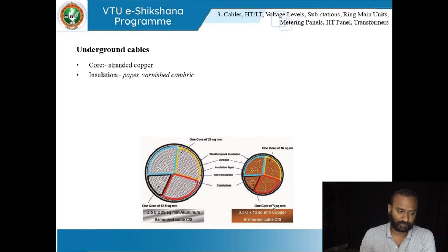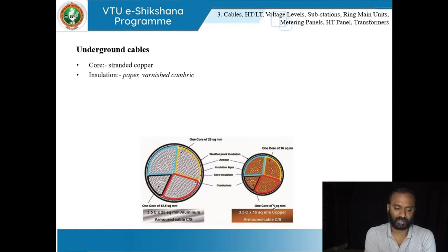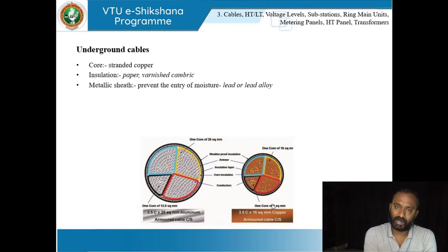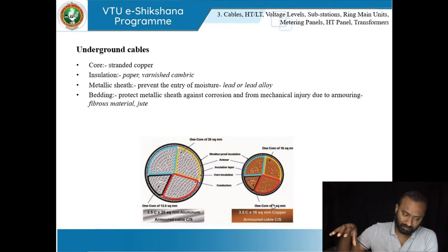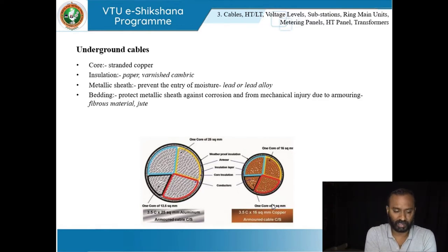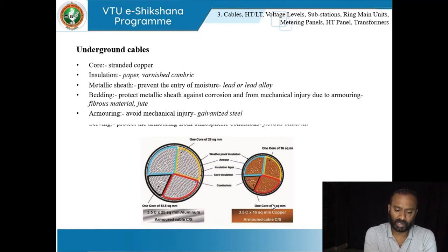These are underground cables. The core is usually made of stranded copper. The metallic sheath — usually made of lead or lead alloy — prevents moisture entry. Bedding is a protects the metallic sheath against corrosion and mechanical injury since the cables are buried underground at a particular depth. Armoring is to avoid mechanical injury and is usually galvanized steel. Serving protects the armoring from atmospheric conditions using a fibrous material.